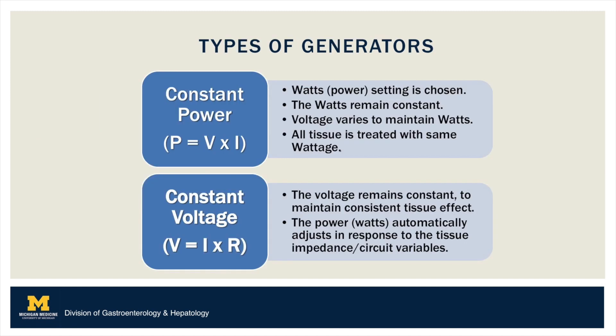Current electrosurgical generators employ either constant power or constant voltage. With constant power generators, the set power is kept at a constant while voltage changes in real time to ensure that the watts delivered to the tissue is constant. In contrast, with constant voltage generators, the power delivered varies with changes in the tissue resistance. Specifically, as tissue resistance increases, current correspondingly decreases to maintain the desired voltage.